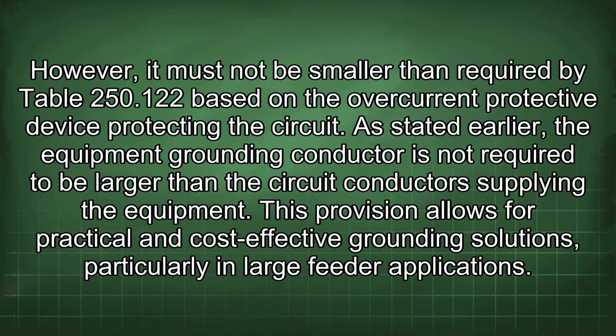However, it must not be smaller than required by Table 250.122 based on the overcurrent protective device protecting the circuit. As stated earlier, the equipment grounding conductor is not required to be larger than the circuit conductor supplying the equipment. This provision allows for practical and cost-effective grounding solutions, particularly in large feeder applications.